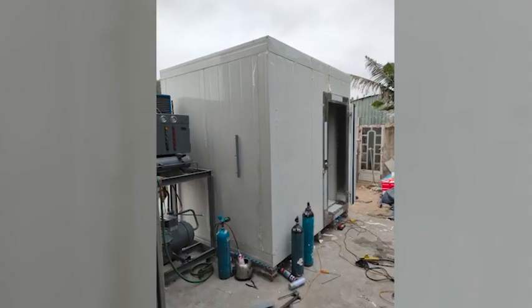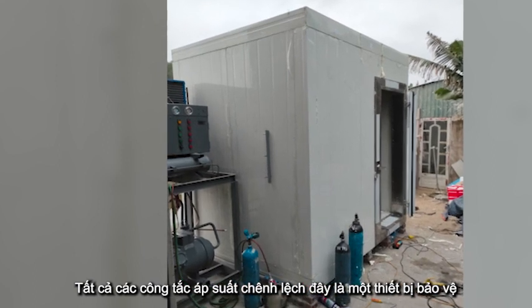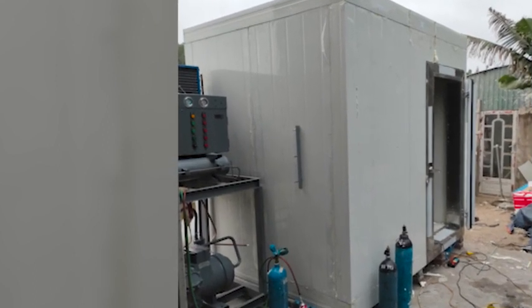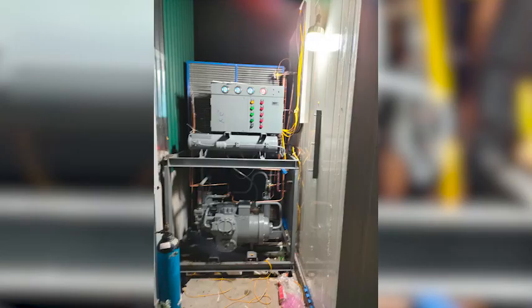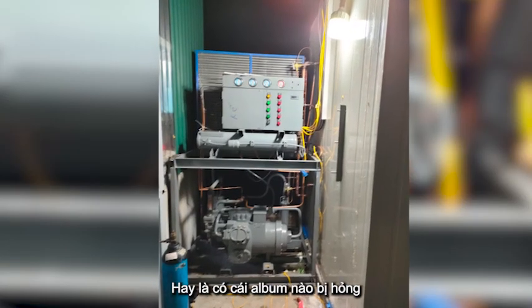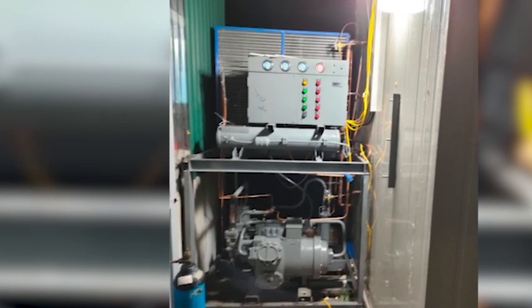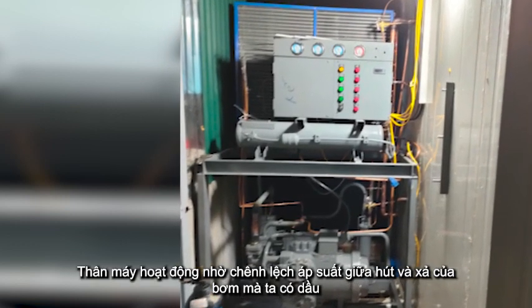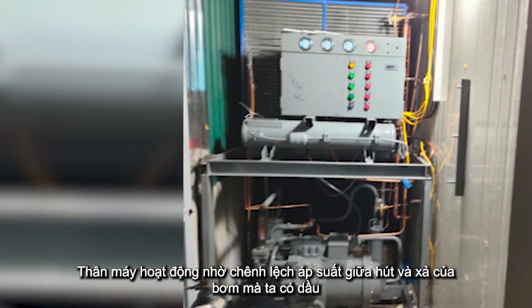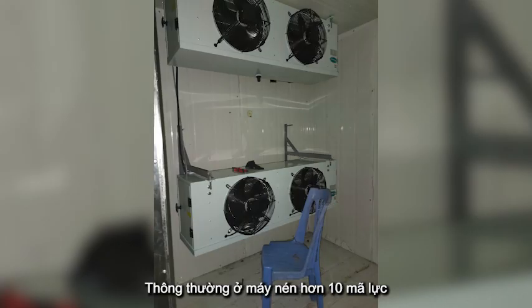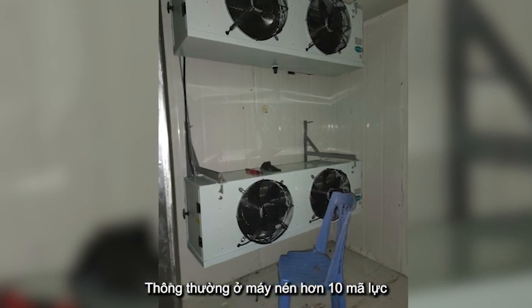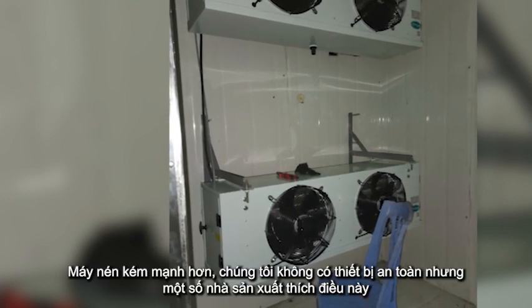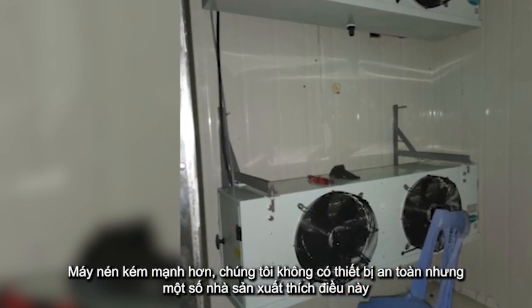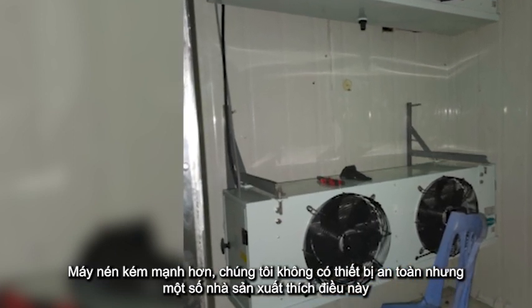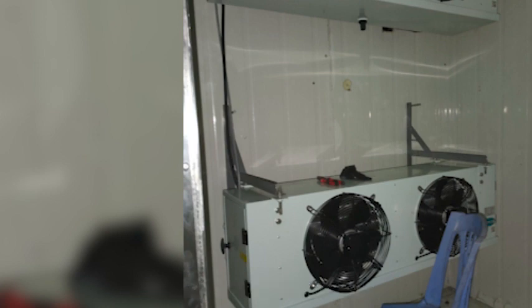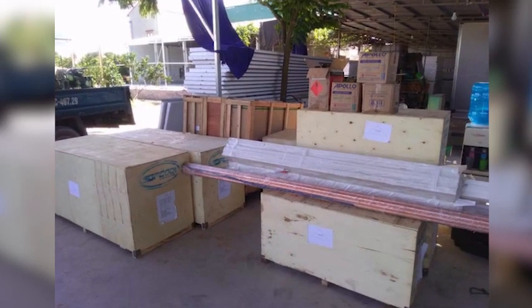Number 3 we have the oil differential pressure switch. This is a protection device that switches off the compressor if there is a lack of oil in the crankcase or if the oil pump is broken. This device works by differential pressure between suction and discharge of the pump. We have an oil pump normally in compressors more than 10 horsepower. In less powerful compressors we don't have this safety device, but some manufacturers like Bitzer have an optical or infrared device to control oil presence in the crankcase.